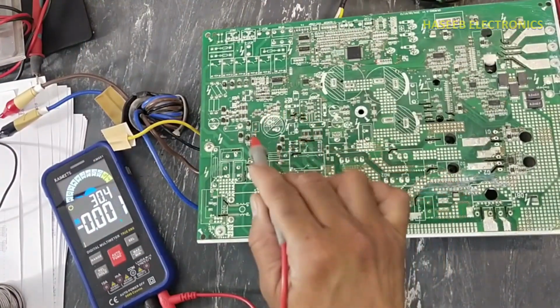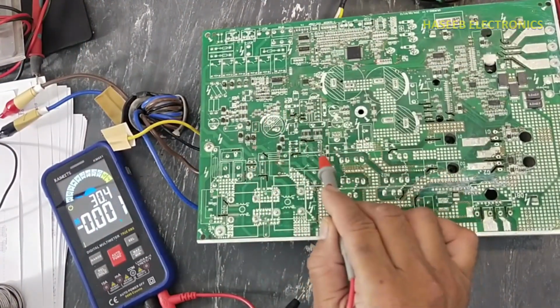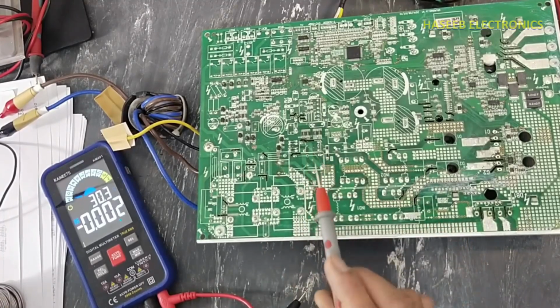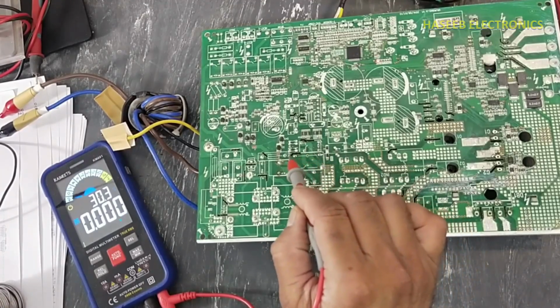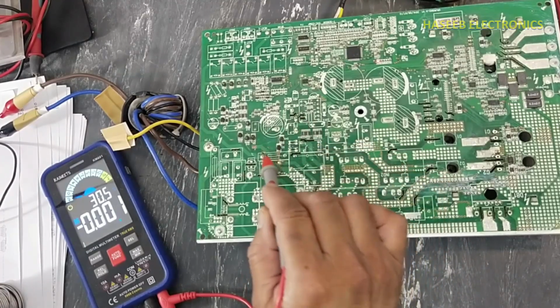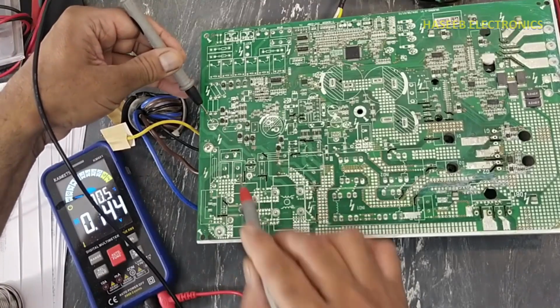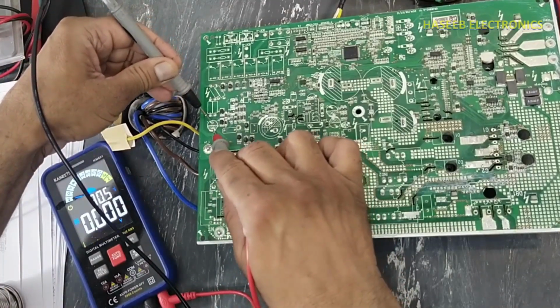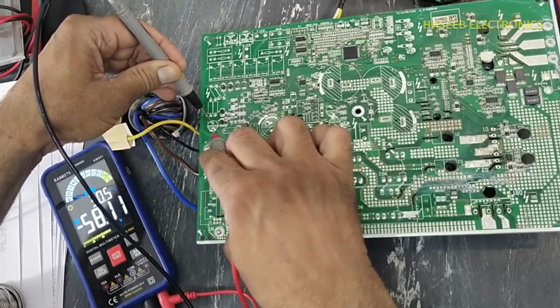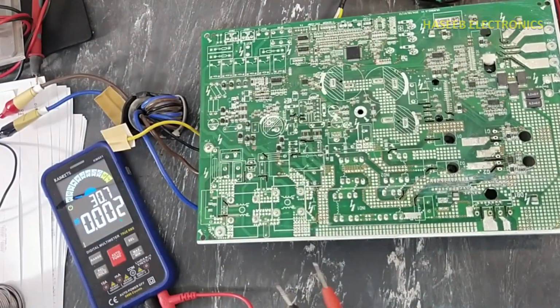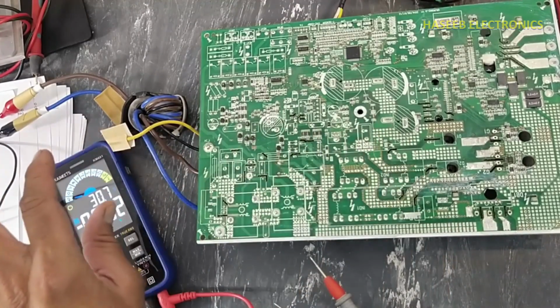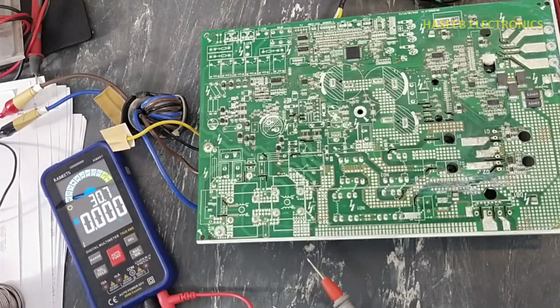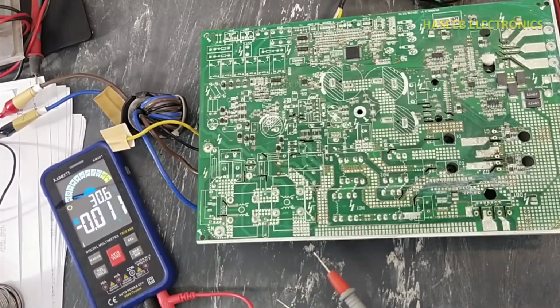In the first step, the power supply must turn on. It will turn on this relay. This relay will close its contacts and supply will pass to the SMPS circuit. Then this voltage will reach the communication circuit. And we can now verify voltage here at the communication capacitor. It is 58 volts. So this supply must be present to send the communication command signal to the indoor units. So these are the power supply checkpoints.